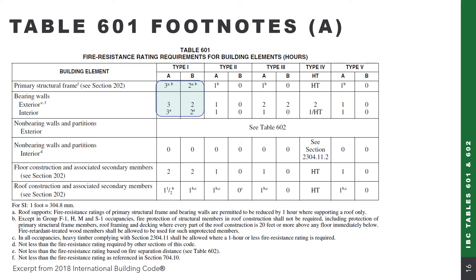Looking at the footnotes in Table 601, Footnote A primarily applies to Type 1 construction and appears under both the primary structural frame and bearing walls interior. Footnote A allows us to reduce the fire rating requirement by one hour when the element is supporting a roof load only. This is significant because, depending on the statistics, typically over 80% of all commercial buildings built in the U.S. are one story only — meaning they're only supporting a roof — making this a critical consideration for Type 1 construction in a one-story building.